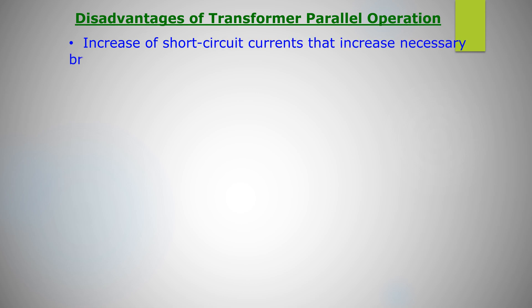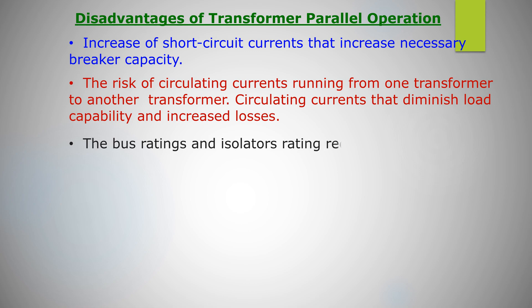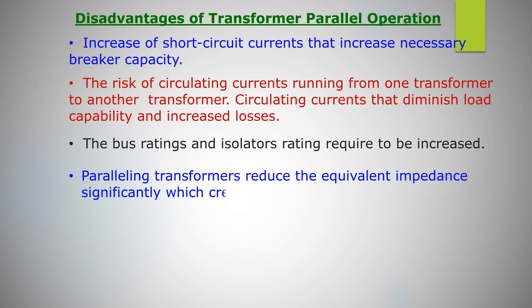Disadvantages of transformer parallel operation: increase of short circuit currents that increase necessary breaker capacity, the risk of circulating currents running from one transformer to another transformer, circulating current that diminish load capability and increased losses. The bus ratings and isolator ratings require to be increased. Paralleling transformers reduced the equivalent impedance significantly which creates high short circuit current in the event of fault.